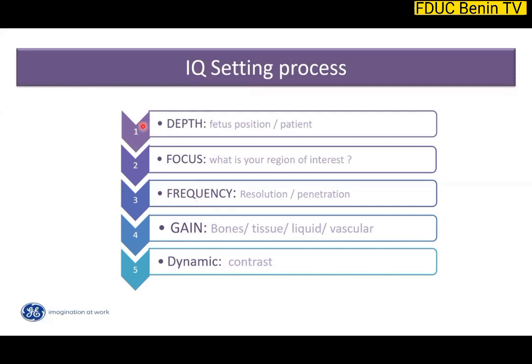That's why the first thing to do is adjust your depth, then adjust your focus. When you're adjusting your focus, the only question that you should have in mind is what is my region of interest, what am I looking at, so that I can put the focus position at the level of this region of interest. Then we will adjust the frequency. If I need more penetration, I decrease the frequency. If I need more image resolution, I use a higher frequency.